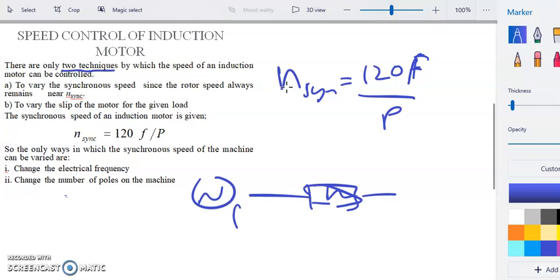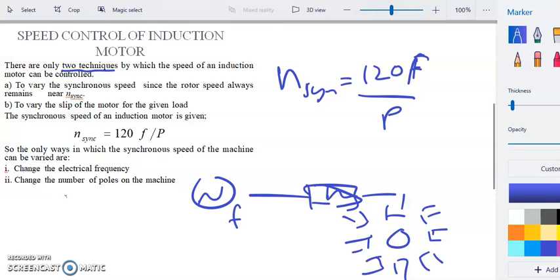So the synchronous speed depends on the frequency of your source, and also the number of poles. You have such things as 2 poles and 4 poles, maybe 8 poles in the construction of your motor. The higher the number of poles, the lower the synchronous speed will be. The higher the frequency, the higher the speed. So you can manipulate the frequency and also the number of poles.